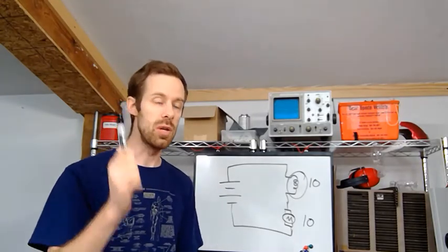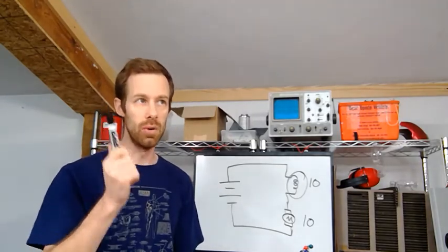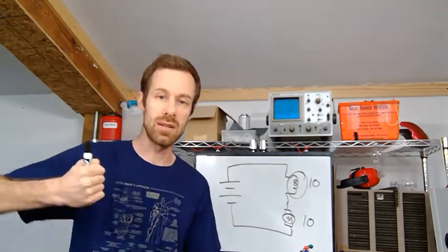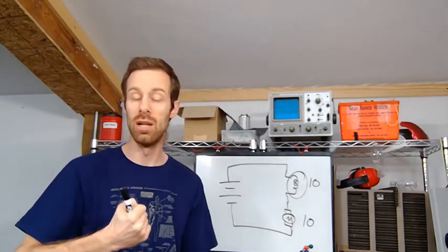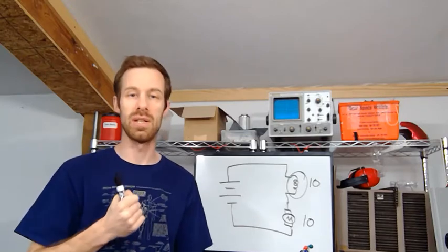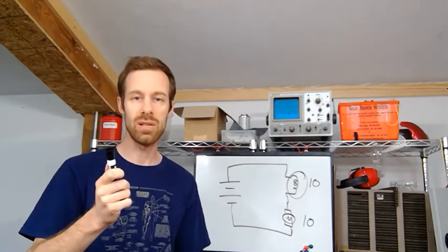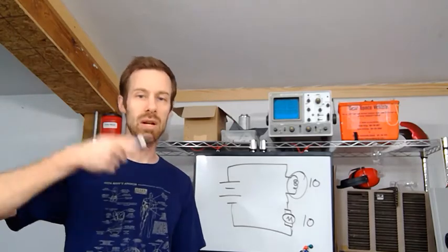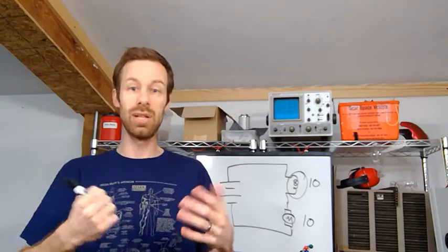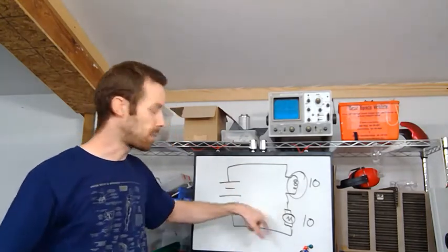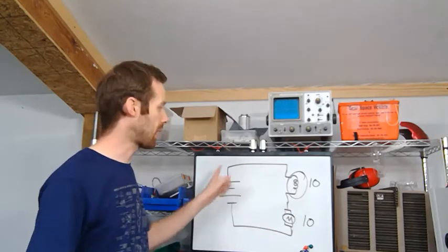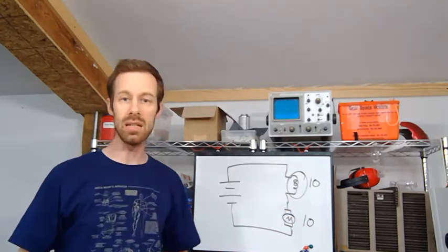Now, when do motors use the most electricity? Motors use the most electricity when they are trying to either start up or when they've been bogged down so much they just lock, they stall. Motor stall current is much higher and the startup current is much higher because it's going the slowest. The faster the motor gets going, the more resistance it has. So as soon as I put a load on that motor and engage the belt or the pulley or whatever it is, then the speed is going to decrease. Therefore, the resistance decreases and the amount of current going through that circuit increases.